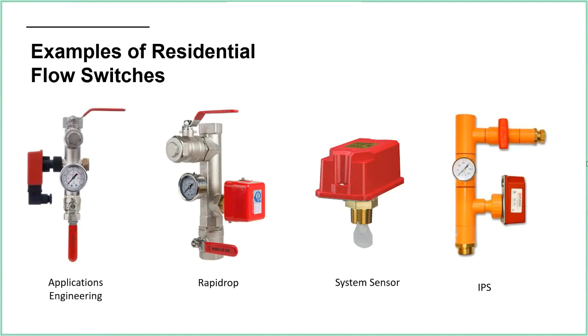One of the things with residential systems under 9251 is approvals. Under 12845, and certainly if you're doing it to LPS 1048 or FIRAS, etc., things need to be approved products, typically LPCB. Under 9251, that's not required. So you'll have a choice really. Some products will be approved and some won't. The flow switches on their own, for example, are approved. The valves, etc., may not be, but it's just something to bear in mind. Approved products are always better.